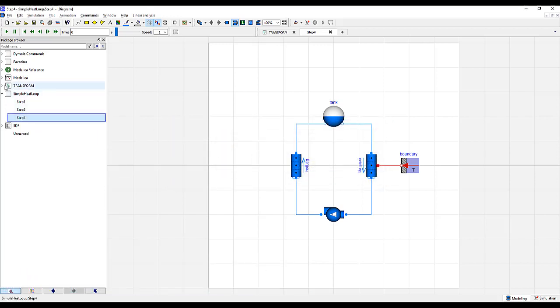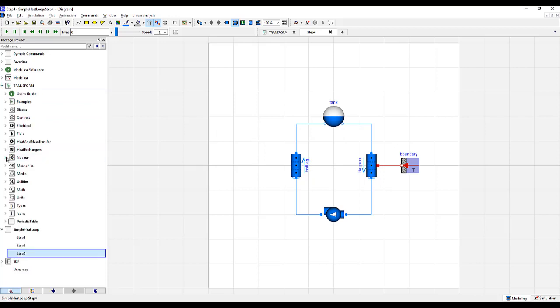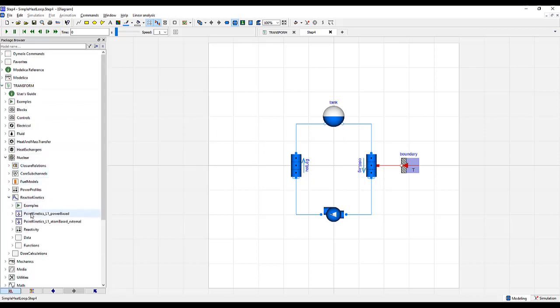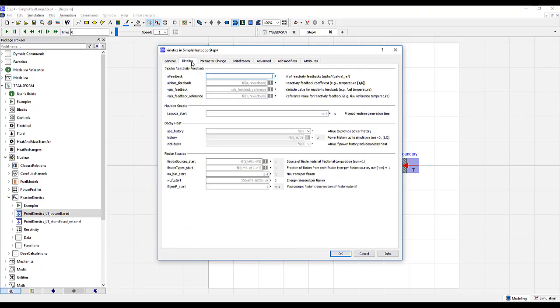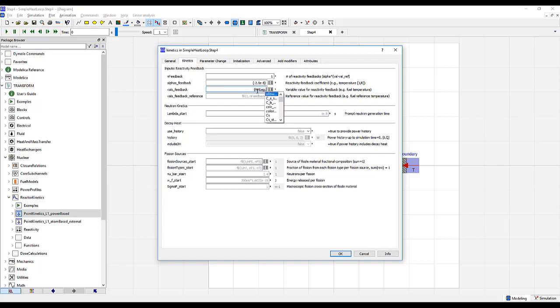Next, go to Transform, Nuclear, Kinetics, and add the point kinetics power-based model. Once there, double click and add in 40 kilowatts to Q-Nominal. Under Kinetics, we want one feedback, which is going to be based on the temperature of the hot leg fluid. Its feedback value will be open bracket, negative 2.5 e to the negative fifth. Make sure to close with the curly bracket. Likewise here, curly bracket. And we're going to be based on this hot leg effective temperature. There is a predefined variable for that already, under Summary, T effective. And the feedback temperature is going to be 92.67. This was something that was pre-calculated. Push OK.